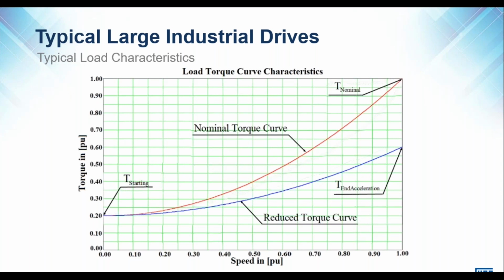One is the red curve. That is a parabolic load curve accelerating from 20% starting torque, you can see on the left-hand side there. And as this load is accelerated, it gets to 100% nominal torque when we reach full speed. However, that does not necessarily always need to be the case, and that's why I've drawn the blue curve. In some applications, you would accelerate the load, and when you get to the end of acceleration point, when you're at full speed, the full load is not yet applied.